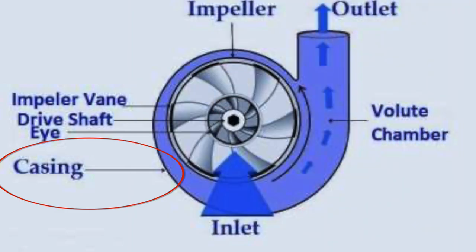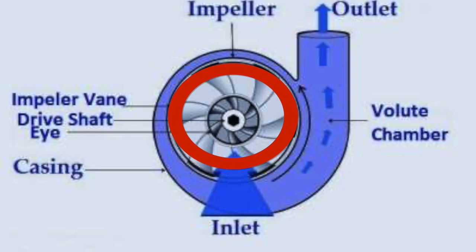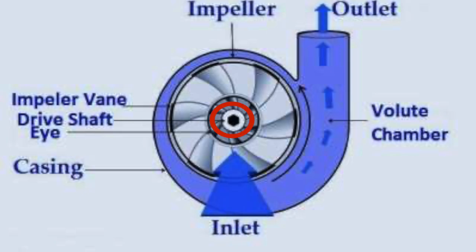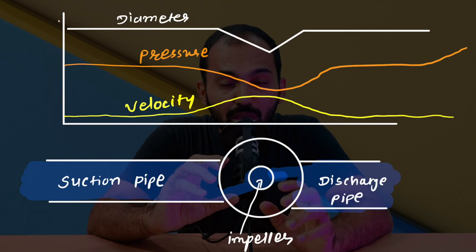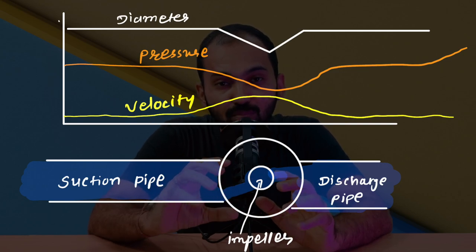Now let's discuss centrifugal pump construction. As you can see in the image, there is a casing with impeller vanes rotating inside. In the middle we have the impeller eye, and at the outlet there is a volute chamber. Fluid comes through the suction pipe, enters the impeller eye, and is pushed through the volute chamber to the outlet. Note that the suction pipe diameter is larger than the diameter of the impeller eye.